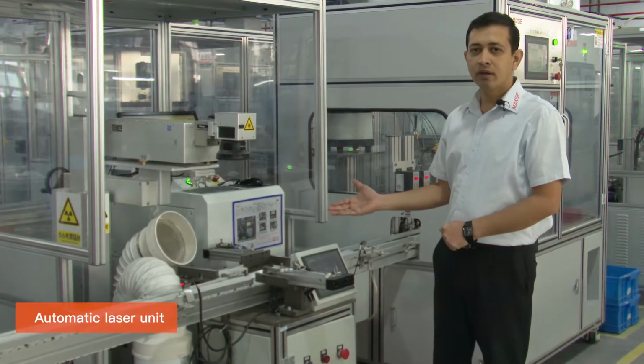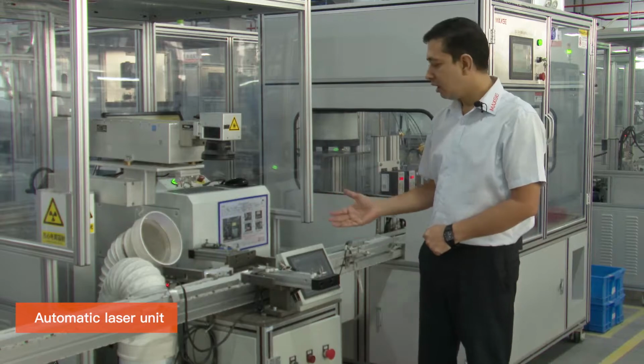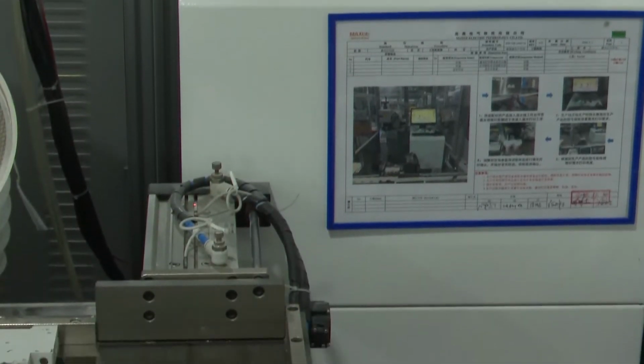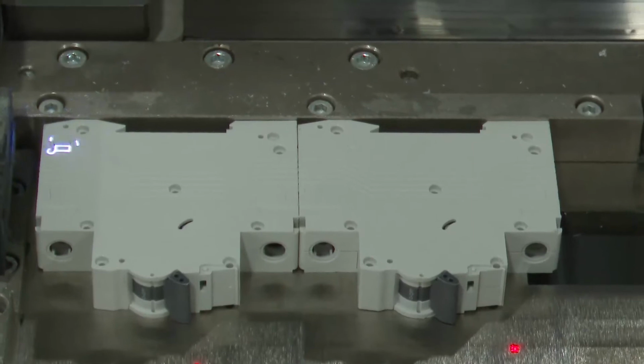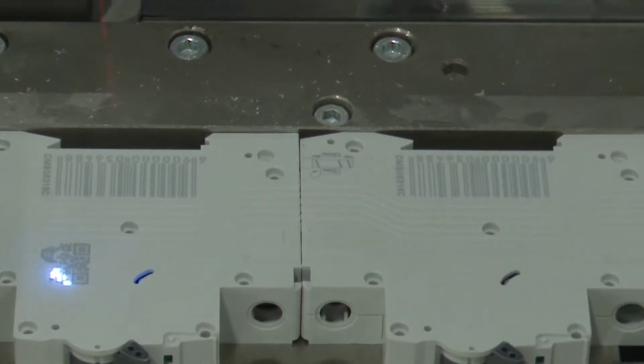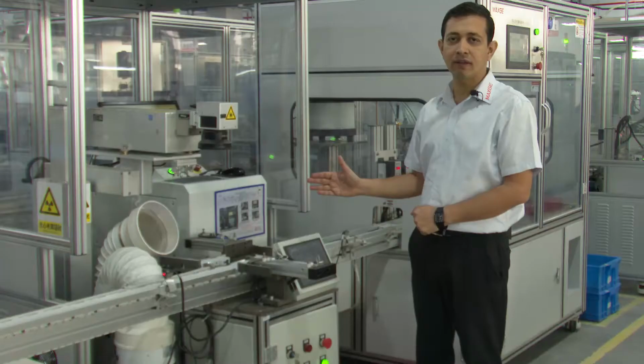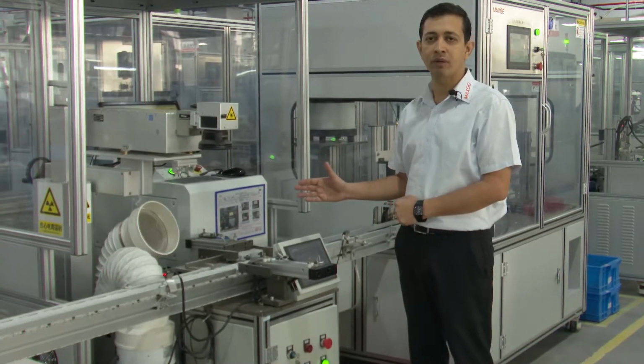Now we are in the MCB testing line. I will tell you how we test the MCB, right from the first stage, which is the laser printing, to the final packing. So let's move to the first station of the MCB testing line, which is the laser printing machine. This is the automatic laser printing machine for the MCB. Here you can see we are printing the QR code on the side face of the MCB, so that with respect to this QR code, the entire data traceability of the testing is saved in the master computer.